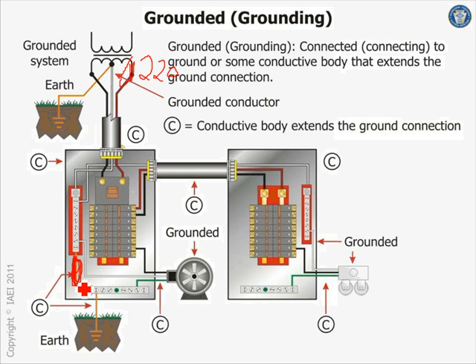Now in the US, we need 25, right? They allow you 25, and in most of the NEC code book, at 25 or less, you don't need a second ground electrode conductor. They don't measure, do you? Unless you do commissioning in buildings, do we guys measure the ground impedance? We don't measure the ground impedance unless you do commissioning in buildings. So there, the inspector, before they approve it, has tools that measure the ground. So 5 ohm is acceptable. And it works, believe me.